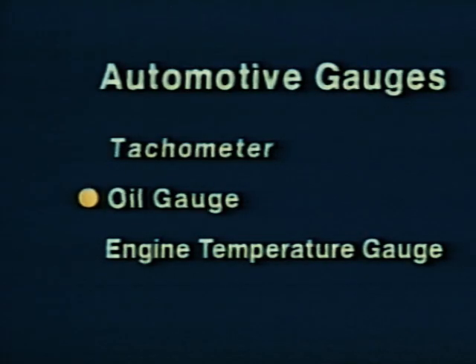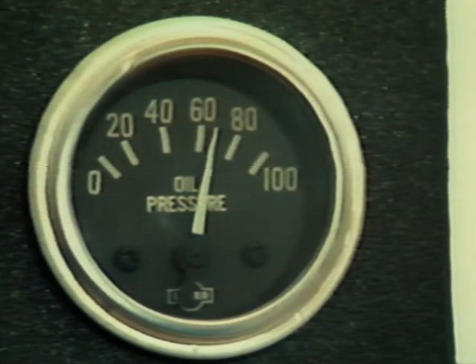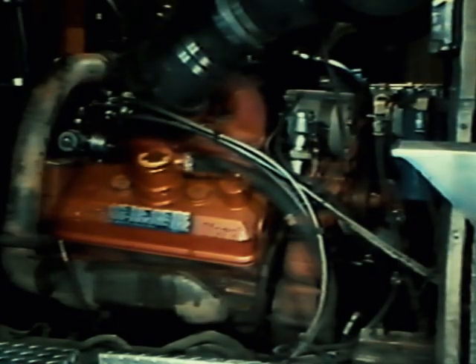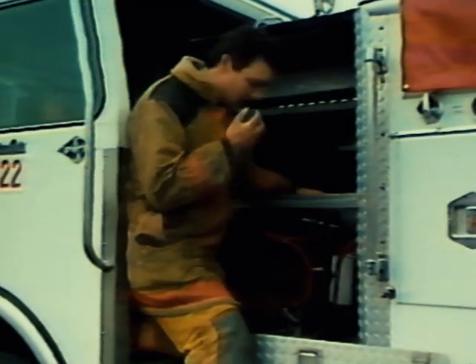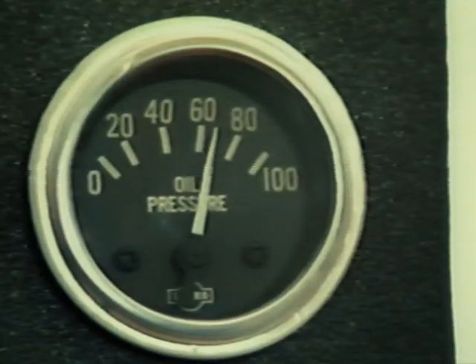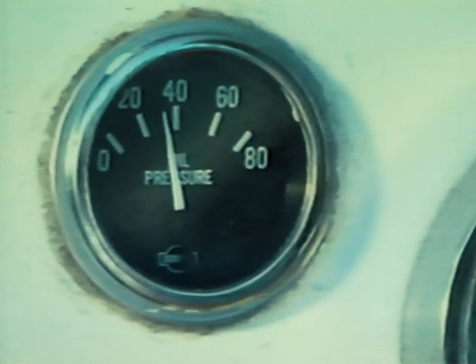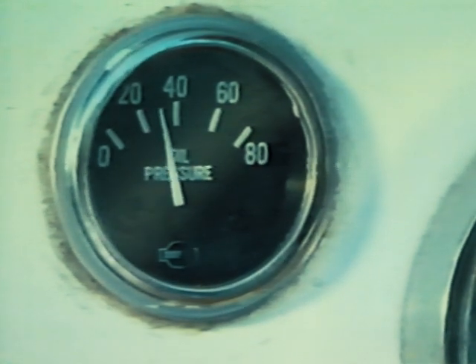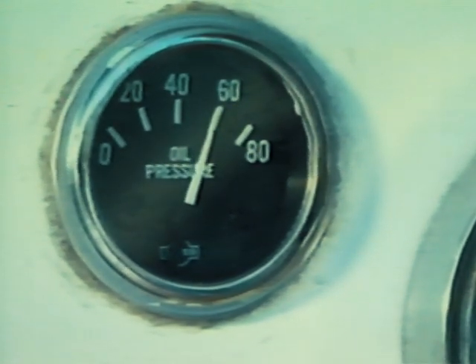The oil gauge on the pump panel indicates whether or not the engine lubricating system is operating properly. This gauge is critical for preventing damage to the engine. Friction caused by insufficient oil or a failure of the engine lubricating system can quickly destroy the engine. Monitor the oil gauge closely during the pumping operation. If the pointer fluctuates rapidly, or if the pressure reading is below the operational level specified by the manufacturer, you should shut down the engine immediately. Continued operation could result in permanent damage to your engine.